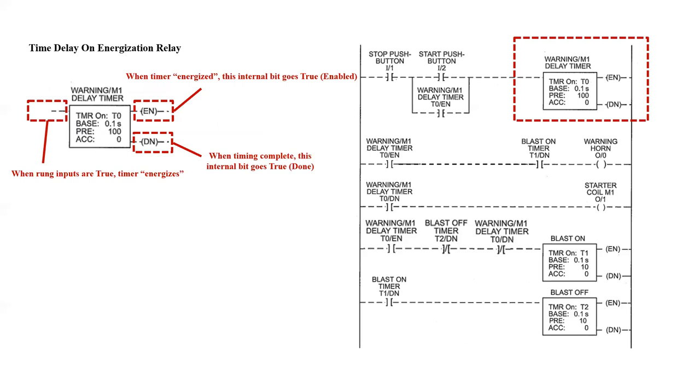Now the time delay on energization relay that we will be utilizing is an Allen-Bradley function that has two separate coils on the output side of the timer symbol. When the timer is energized, the EN or enabled internal bit will go true. When timing is complete, the DN or done internal bit will go true.